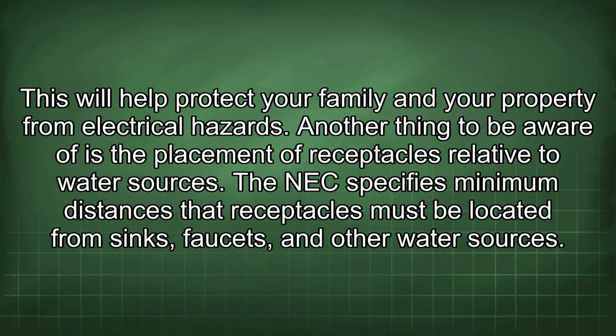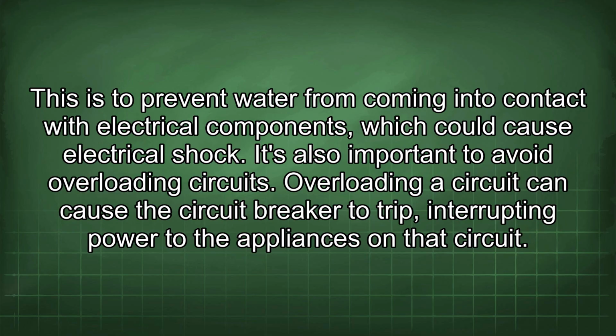Another thing to be aware of is the placement of receptacles relative to water sources. The NEC specifies minimum distances that receptacles must be located from sinks, faucets, and other water sources. This is to prevent water from coming into contact with electrical components, which could cause electrical shock.